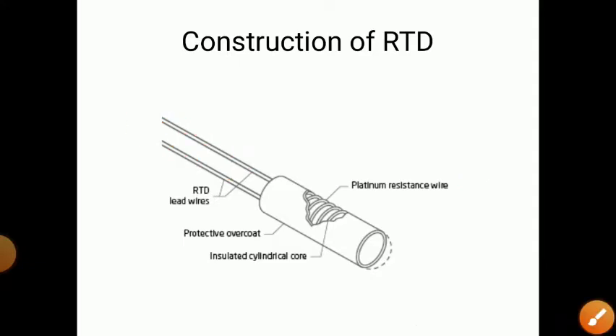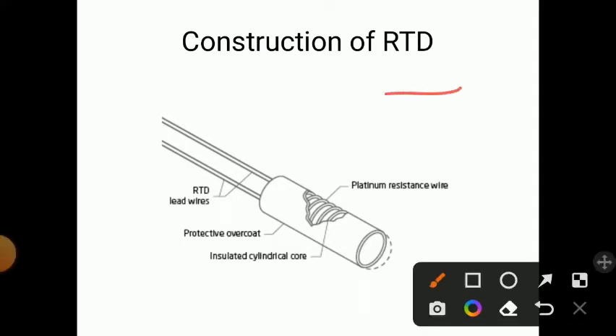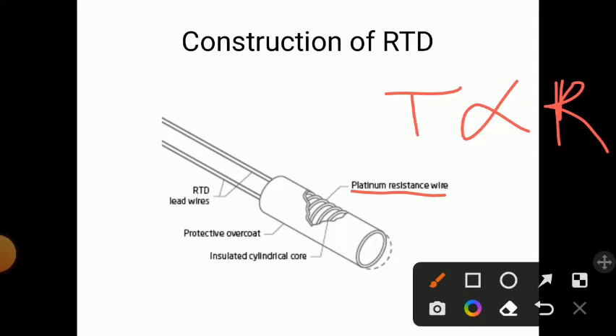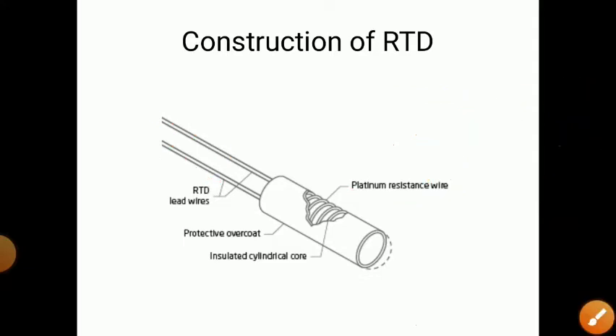The principle of RTD is: as temperature increases, resistance also increases — temperature is directly proportional to R. This platinum resistance wire already has some resistance like 100 ohm or 120 ohm; that is its fixed resistance. But as temperature increases, this resistance also increases. So input is temperature change and output is change in resistance, which is measured between the two wires.